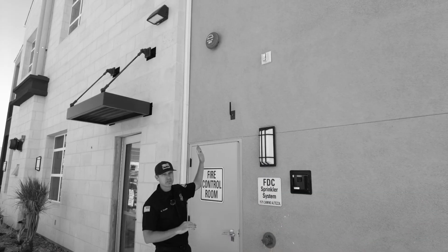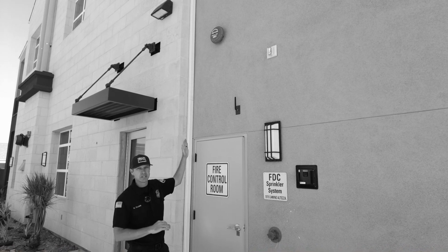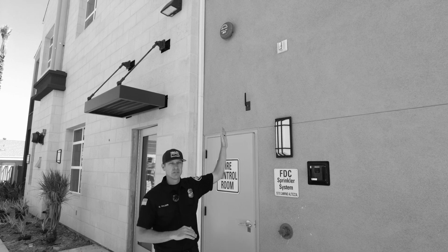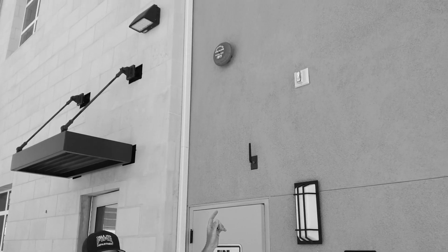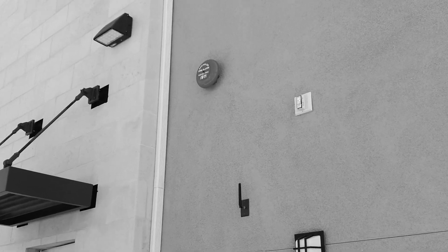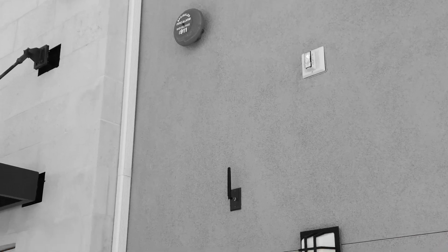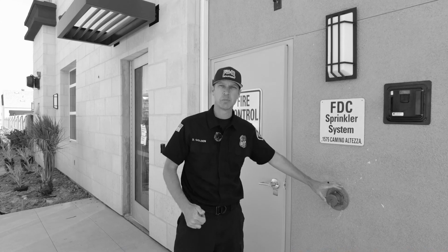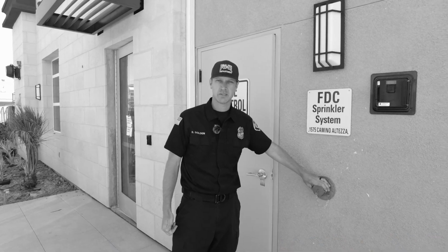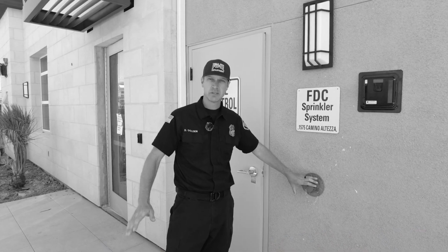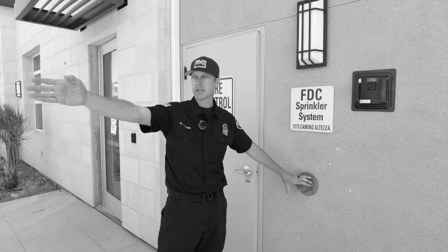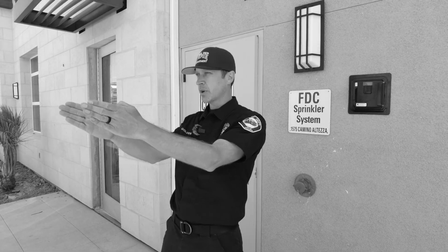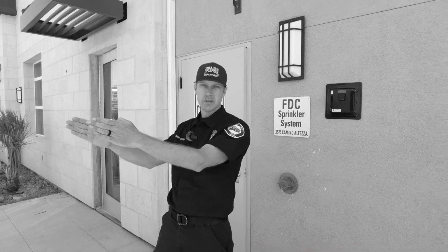In addition to your typical exterior sprinkler bell letting you know water's flowing, you also have an exterior strobe only device. The only purpose of this strobe is to let you know water's flowing in the system, and it'll be perpendicular to your FDC device, whether it's wall mounted or exterior mounted out in an island or in the parking lot. You can look at that device and look out in your parking lot and locate your FDC and PIV.